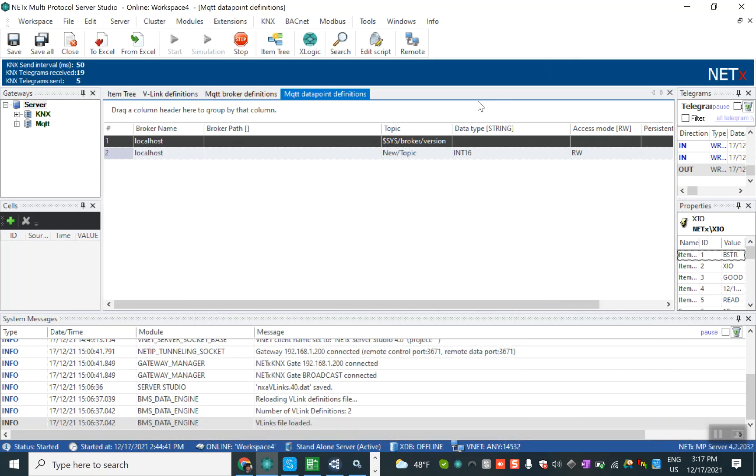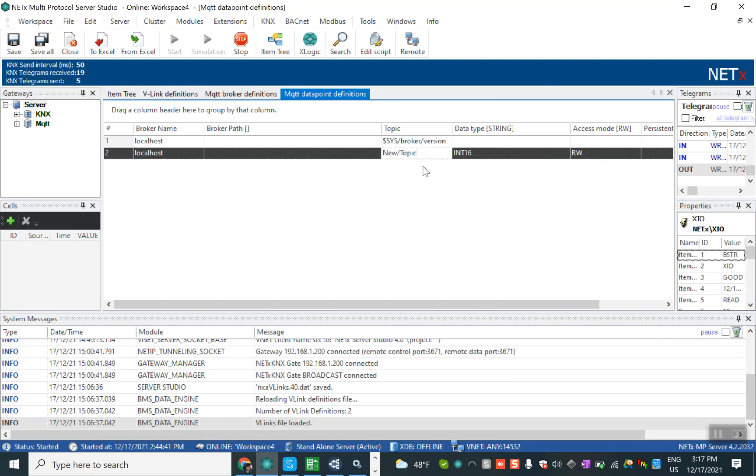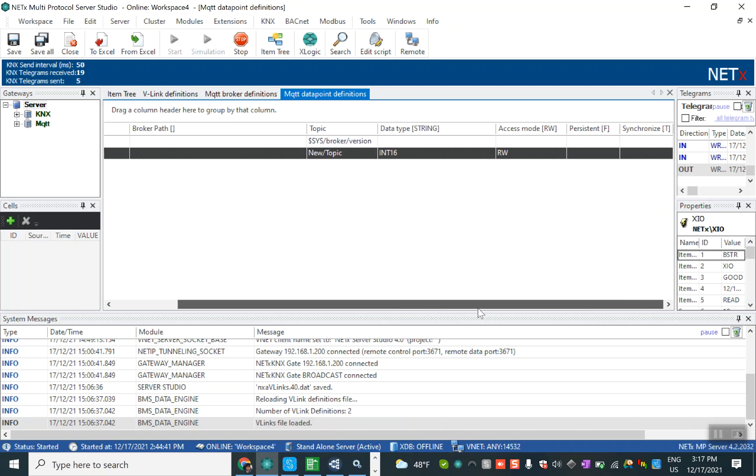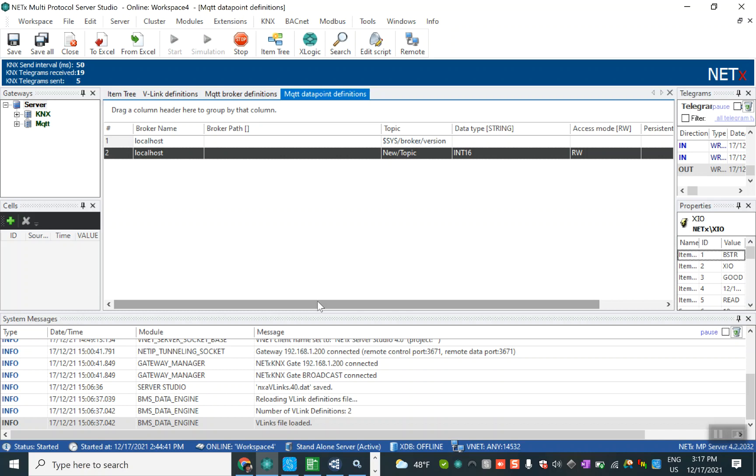Here we put the new topic. The data type is integer 16 bits because we want to send the set point from the MQTT to the KNX system. The access mode is read and write, both of them together, and that's it, it's done.